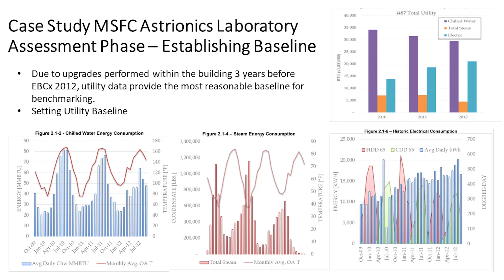Part of the effort is doing the baselining. So what we did is take 3 years worth of data on steam, electrical, and chilled water. There's a central plant, so everything was coming from the central plant for steam and chilled water. We looked at how that energy consumption was, then normalized it using weather data, because you don't have two years that are ever the same as far as energy consumption. Until you normalize that data, you're not comparing apples to apples. That's basically what's in these charts.